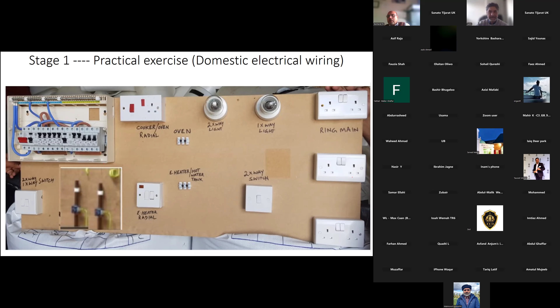So behind this screen, we have got 3 sockets as well. Say, for example, our fault is in a one-way switch. What is a one-way switch? It is a lighting circuit. Over here, we will see which circuit breaker is for the lighting circuit. We turn that circuit breaker off, and then we remove the live wire from here. Then we open this one-way switch and see where there may be a loose wire. Because the circuit breaker is off, you are safe. You can reconnect that wire.